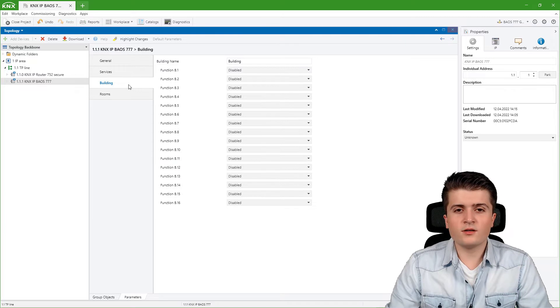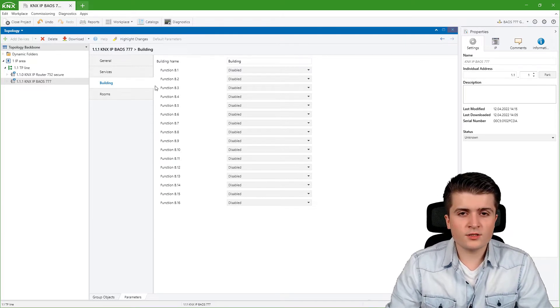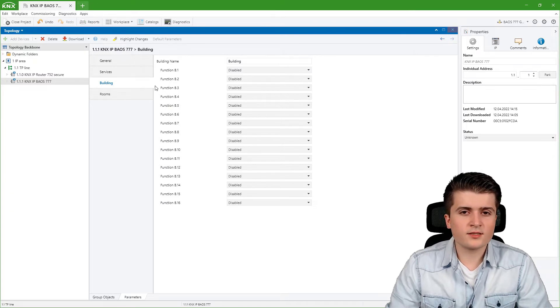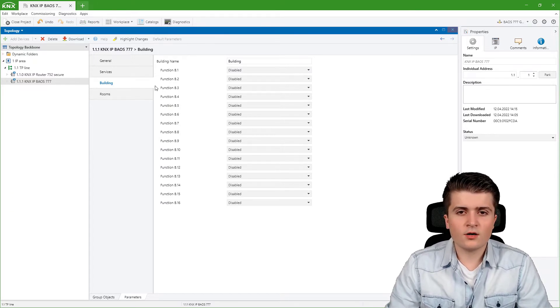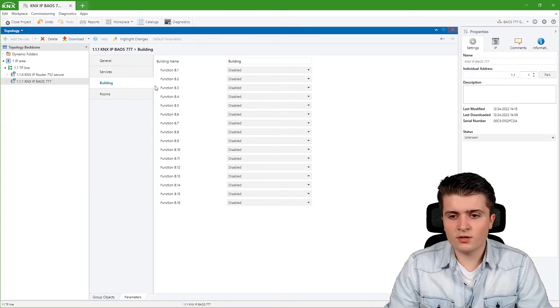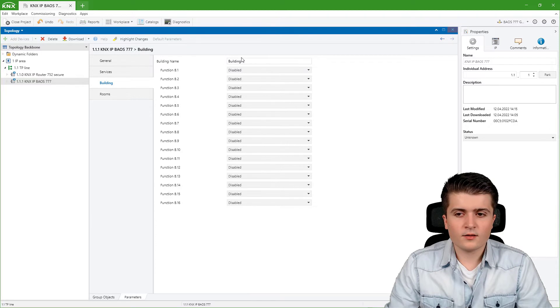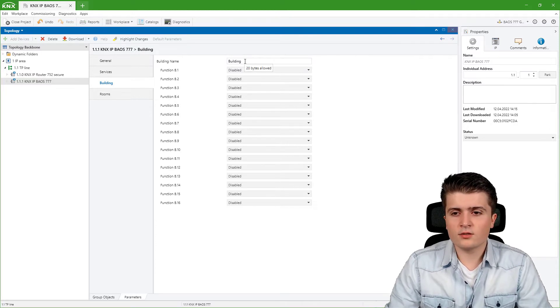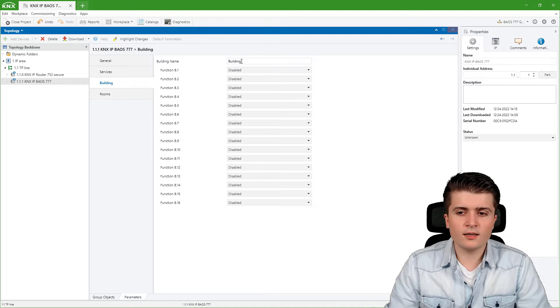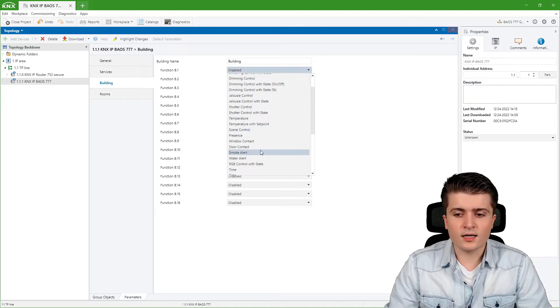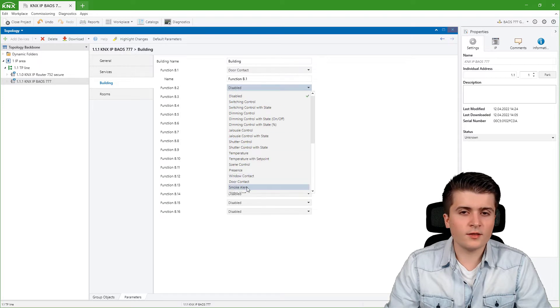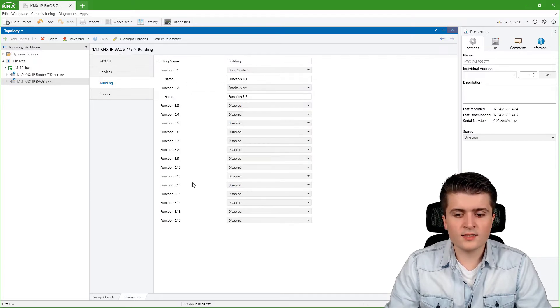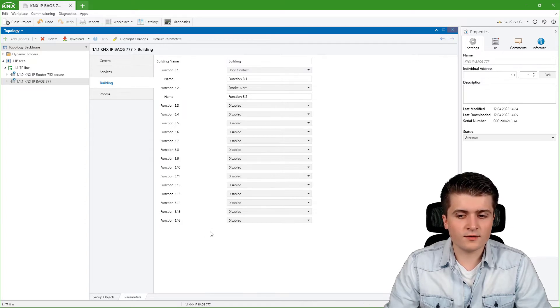On the building page here we can create functions that are not associated to any room, for example information from the weather station or from window and door contacts. We can give this page its own name. I'll stick to the default name building and then we can enable for example the door contact function or the smoke alert function. We have up to 16 functions that we can activate.